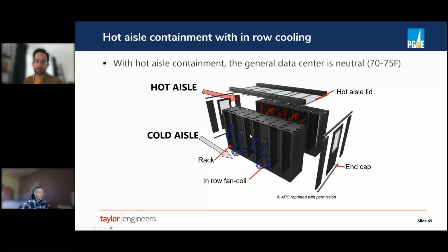So there isn't a lot of pressure drop to your ductwork because there is no ductwork. Big downside of this, of course, is that it doesn't have an air economizer. So it's relying 100% on chilled water or whatever fluid you're bringing to your cooler, in-row cooler.